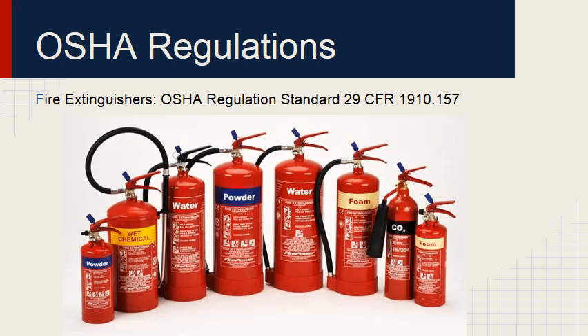Assure that portable fire extinguishers are maintained, fully charged, operating properly, and kept in designated places at all times, except during use. Remove from service all soldered or riveted shell, self-generating soda acid, or self-generating foam or gas cartridge water-type portable fire extinguishers that are operated by inverting the extinguisher to rupture the cartridge or to initiate an uncontrollable pressure-generating chemical reaction to expel the agent.